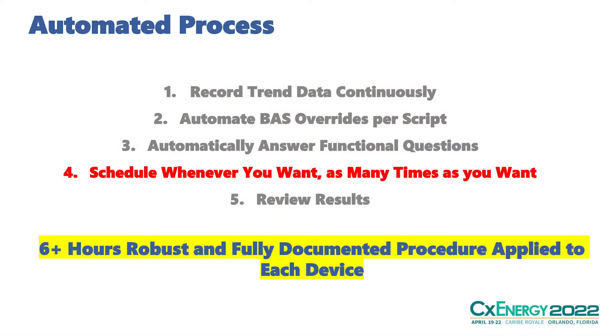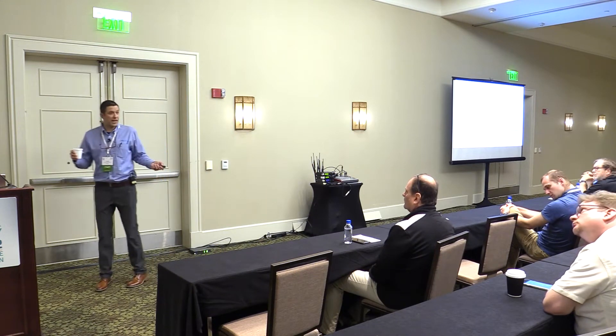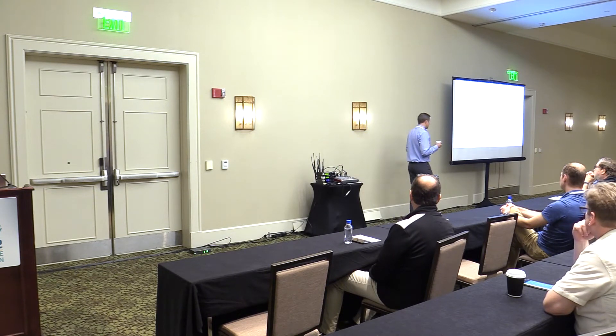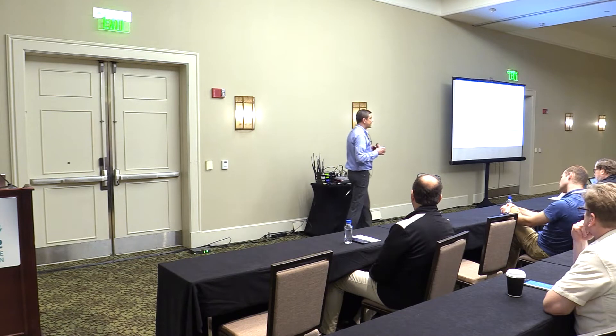In contrast, with an automated functional testing process, you can do whatever method of script you want, for as long as you want. We've done radiant systems where it takes longer for spaces to react to radiant cooling or heating — who's going to sit there and wait two hours to see how long it takes for a space to come up or down to temperature? Normally for a VAV box you put it in heating mode, see if the valve starts to open and temperature starts to increase, then move on. But that leaves a lot on the table. A positive reaction is not a positive conclusion. Being able to extend your test script to whatever duration you want is quite a luxury.